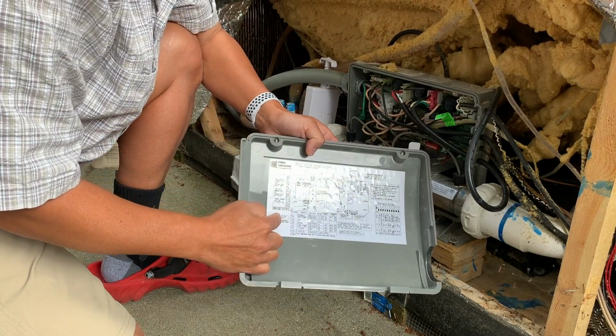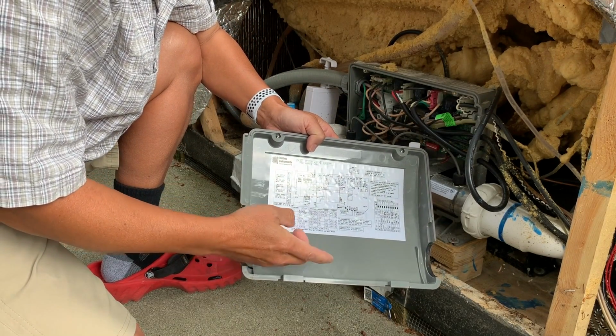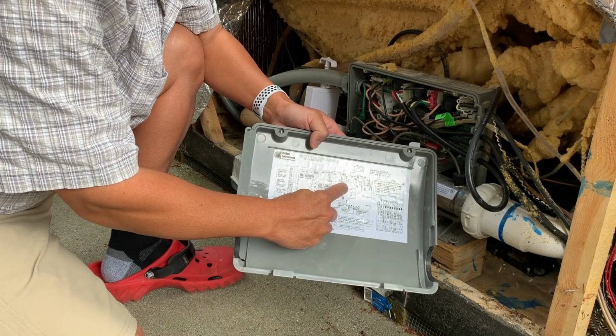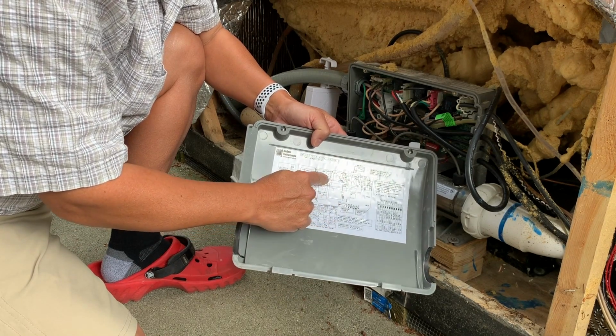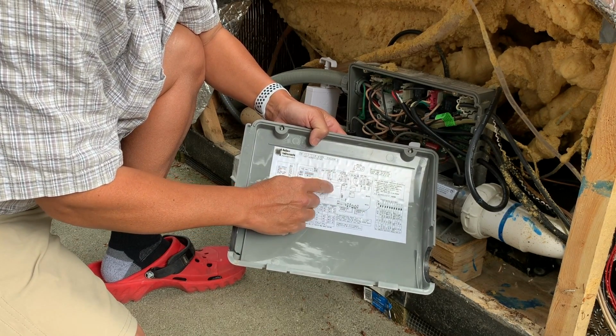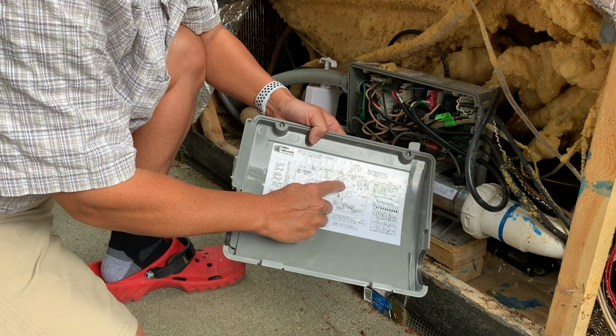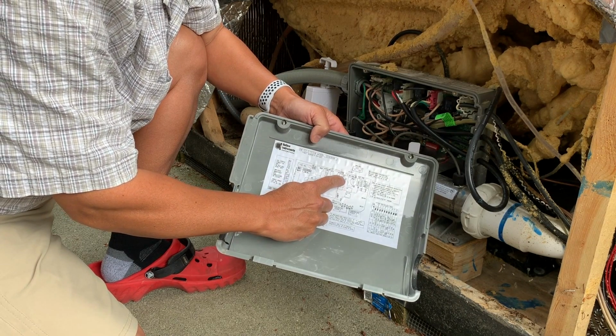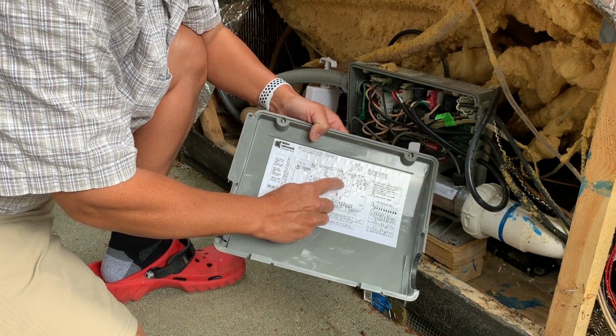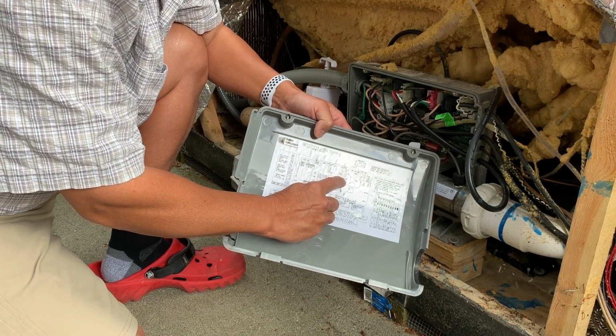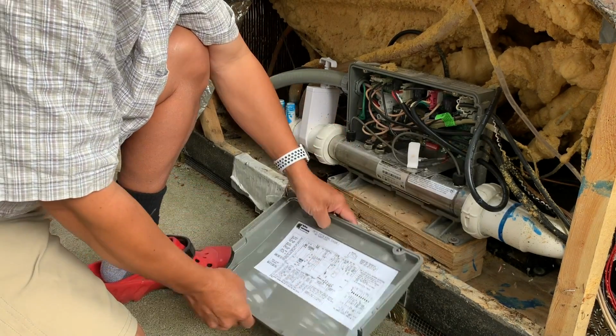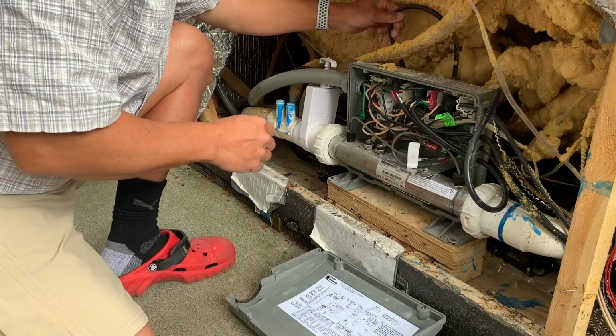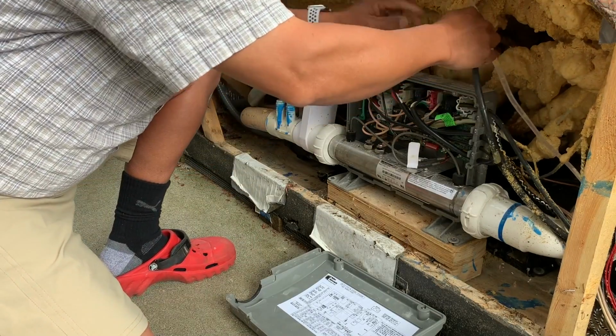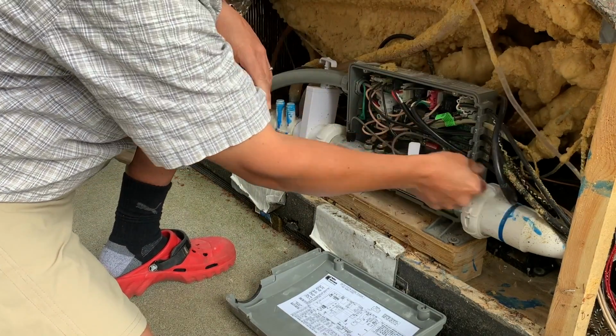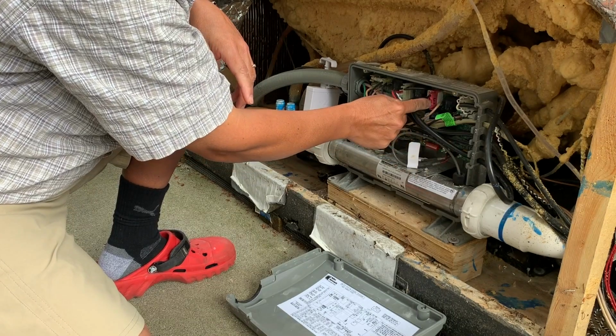Inside the cover is a wiring diagram, and on the wiring diagram we see that pump number 1 plugs in here on jumper J23. Pump number 2, designated as blower/pump 2, is plugged into jumper J17. You can also just trace the wire from the pump and follow it to see where it plugs into the board here.